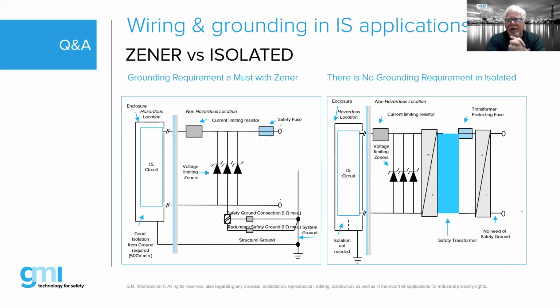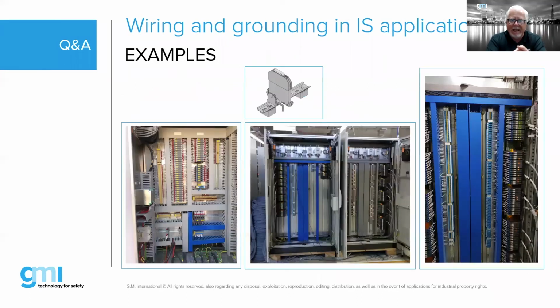The only thing I would add to it is that generally in the IEC world, and it's reflected also in the EN standards, the minimum size, if we're using a single conductor for an IS circuit, must be 4 millimeter or greater. If we're using a redundant or 2 grounds, if you will, they can be 1.5 millimeter. So as far as the size. And I took a little picture here to show how to ground that.